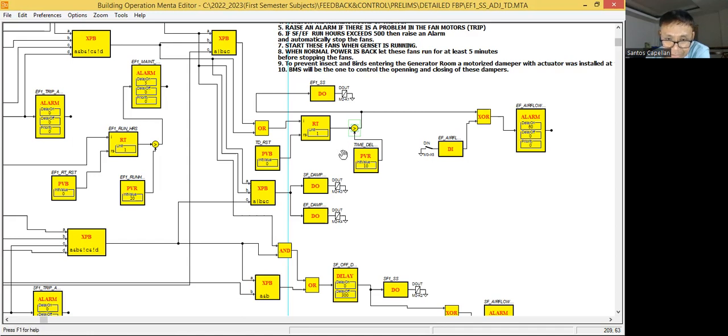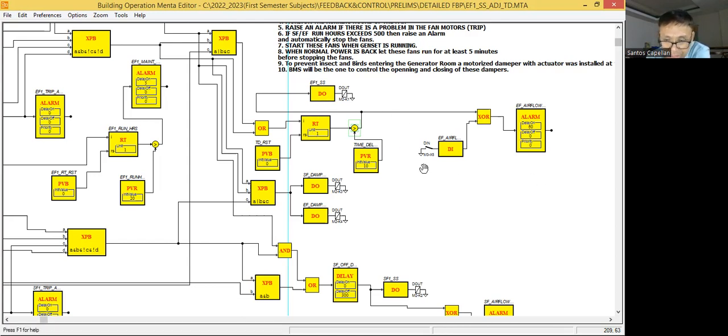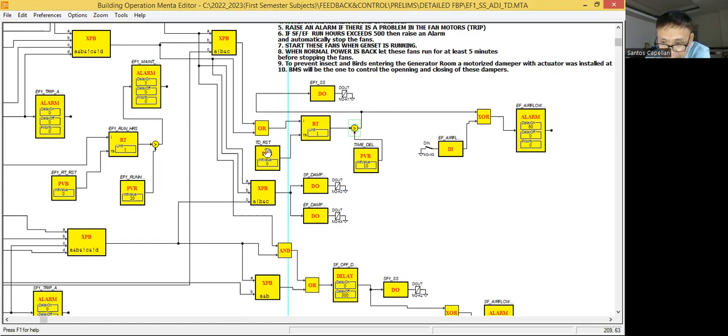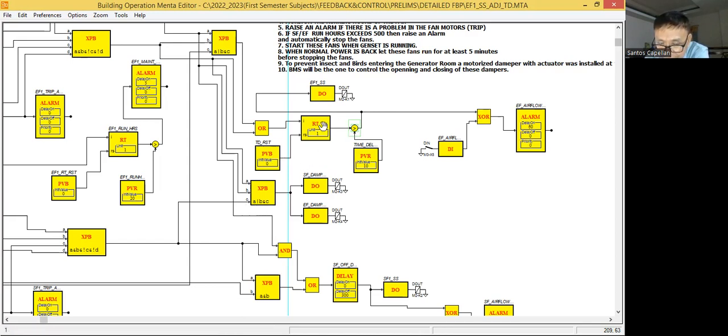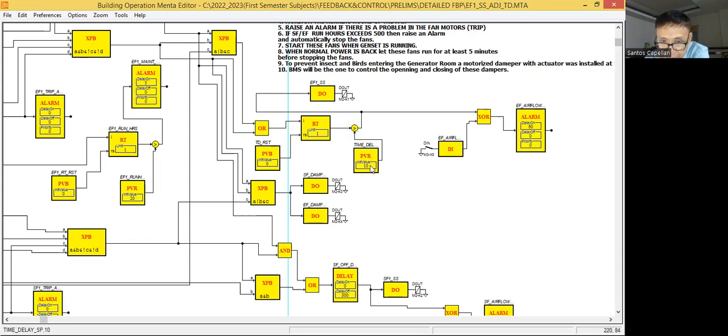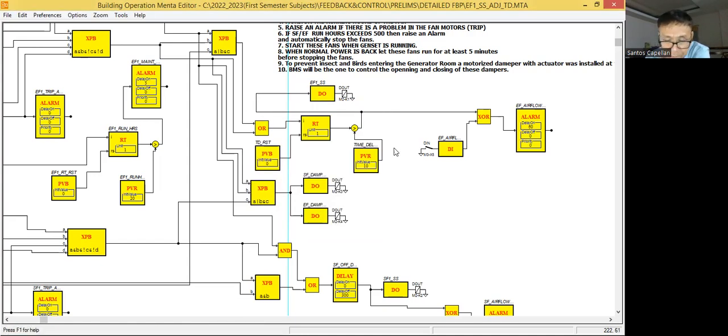This is a possible way of implementing what he's asking for. Now the main concern here is how are you going to automatically reset this runtime. Because once the output of this block exceeds this set point, this will be my time delay set point, this is the user adjustable. So when this block output exceeds this, then that's the only time it will give the one signal to start the EF1.